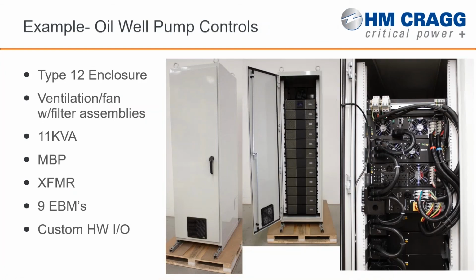I mentioned oil and gas. So oil well pump controls in a Type 12 enclosure, 11 kVA of UPS. You guys are familiar with the 9PX 11K, it has an external battery already and a transformer. Well, this customer needed some ungodly number of hours of runtime, so we included 9 EBMs.